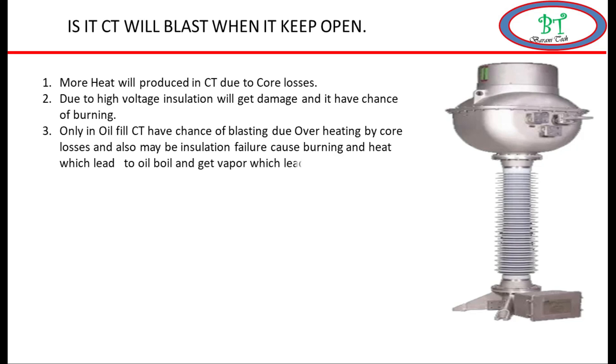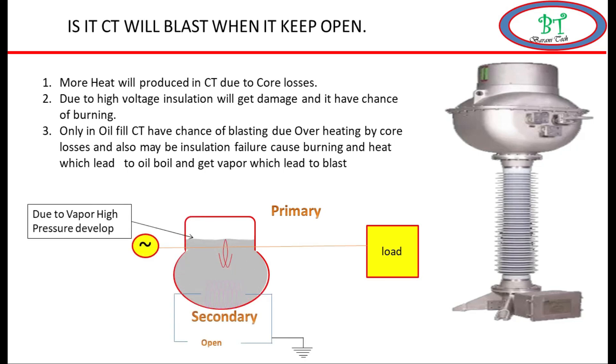CT has a high chance of blasting due to overheating by core loss and also by insulation failure which leads to boil the oil and get it evaporated. This evaporate is accumulated at the top of the CT which makes high pressure and leads to blast.